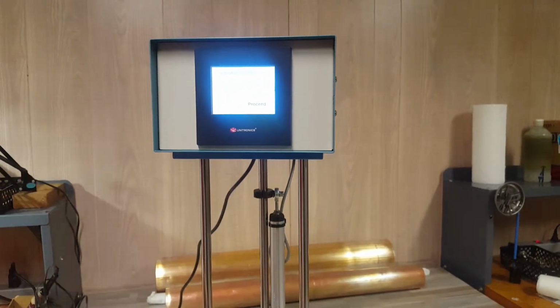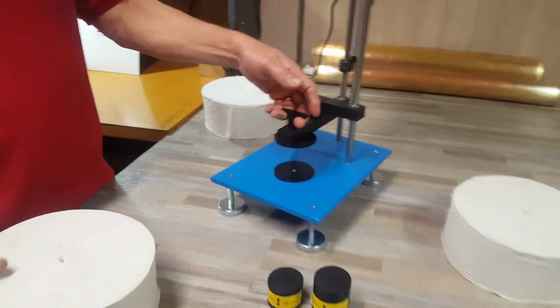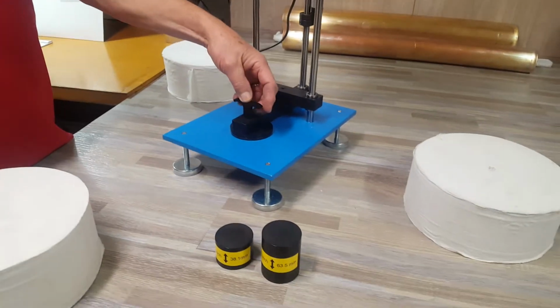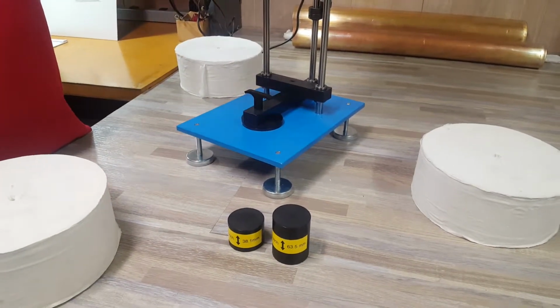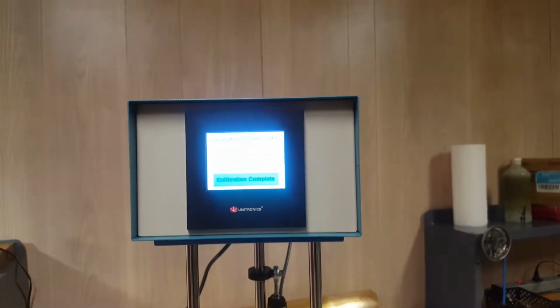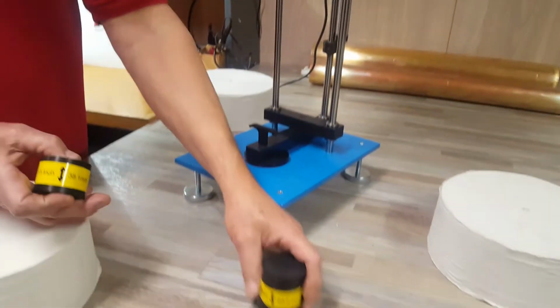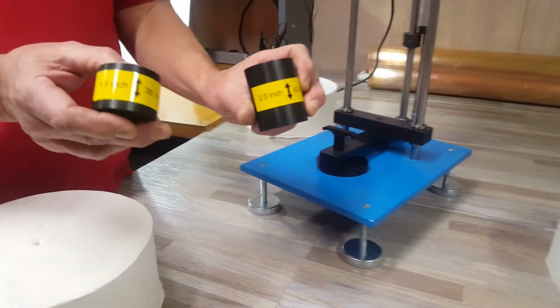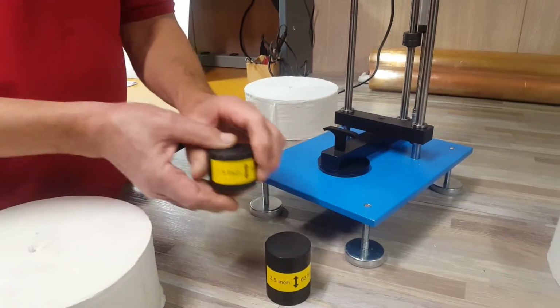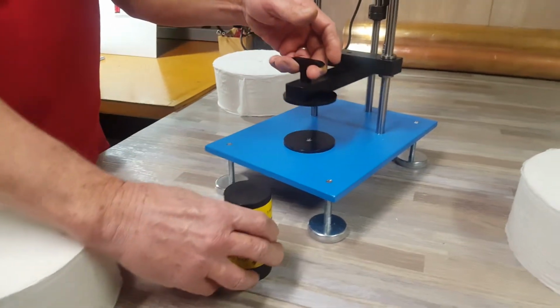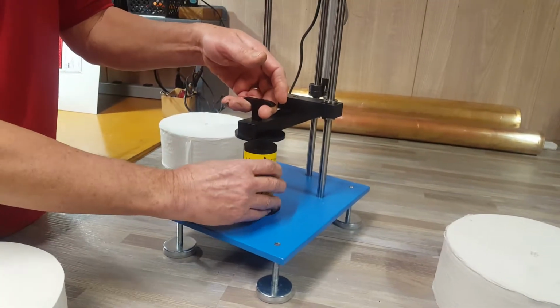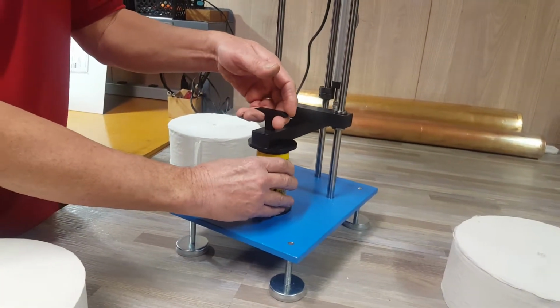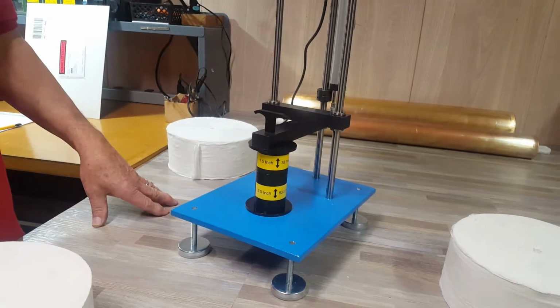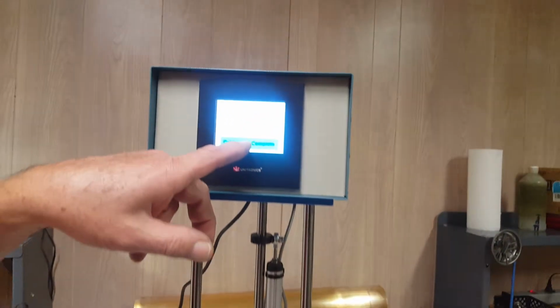For starters, it's telling us to remove the sample and lower the caliper to the base to establish our 0 position. I just touch to proceed, and now it's telling me to take the 2 gauge blocks that are provided with the instrument. We have a 2.5 inch and a 1.5 inch high gauge block, and it's instructing us to lift the caliper and place both of those gauge blocks in to establish a 4-inch reference. Now I'm going to touch the green calibration complete button, and our calibration is done.